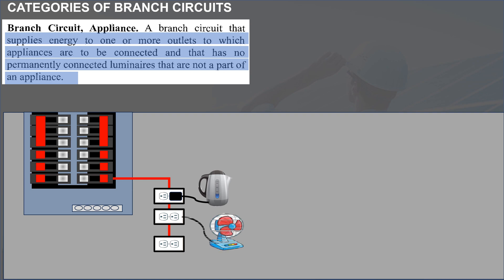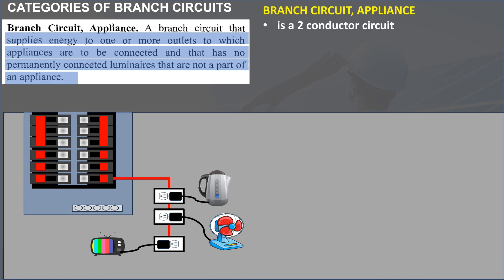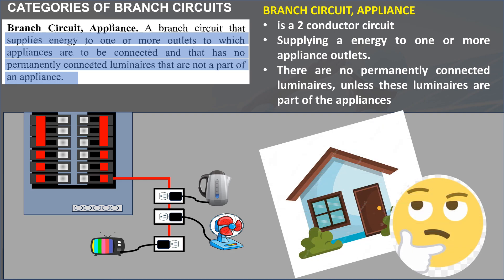The branch circuit is categorized into the following. First, branch circuit appliance: a branch circuit that supplies energy to one or more outlets to which appliances are to be connected, and that has no permanently connected luminaires that are not part of an appliance. Therefore, a branch circuit appliance is a two-conductor circuit that supplies energy to one or more small appliance outlets, with no permanently connected luminaires unless they are part of the appliances. Branch circuit appliance is an important term when designing an electrical system for dwelling units.